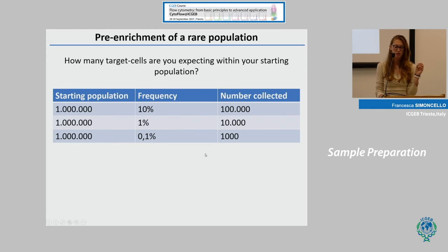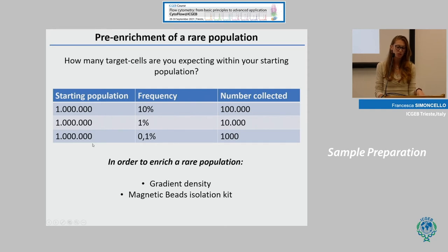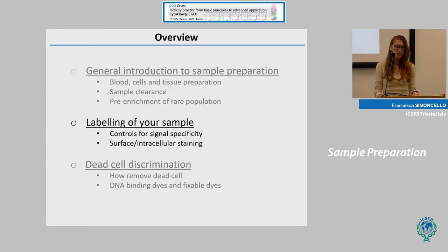Another point to consider is how many target cells you expect within your starting population. For example, if you acquire 1 million cells and your target population is 1%, you collect 10,000 cells, which is quite enough. However, if the frequency is 0.1%, you acquire only 1,000 cells, which from a statistical point of view is not enough. You could acquire a higher number of cells, but this wastes time and can block the instrument. Another option is to enrich rare populations using density gradient such as Ficoll, or isolation kits based on magnetic beads.